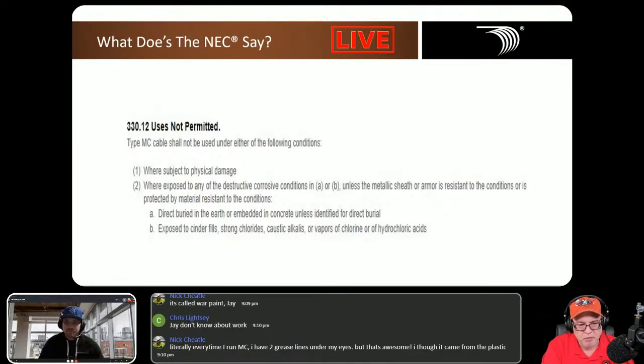Condition B covers exposure to cinder fill, chlorides, caustic alkali, vapor of chlorine or similar. PVC is very resistant to these. As of 2020, it's been clearly stated in 680 for pool applications that you can use MC cable because the PVC jacket is resistant. If you look at the list of what's considered acceptable for corrosive environments, it doesn't specifically say MC because MC is listed, and the PVC jacketing does meet that condition of use, despite what anybody wants to say. Some people just don't know how to read the code, because that's exactly what it says.